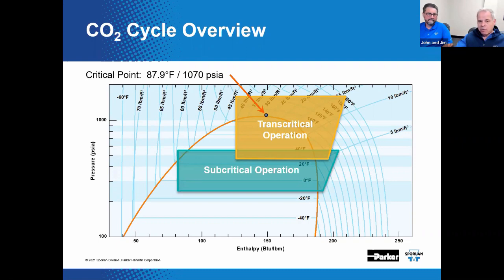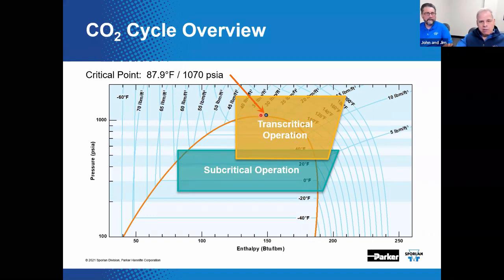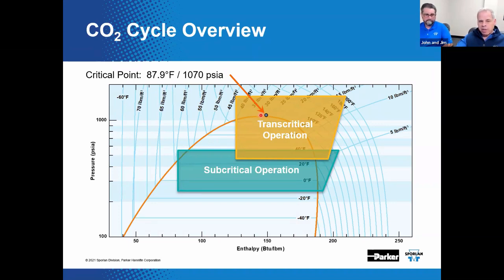Designs typically have two modes of operation. Could have transcritical and or subcritical. Now, what is the critical point? What does that mean? The critical point is up at the very top of the dome. Is that it right there? Yep. And basically above that point, you cannot achieve a state of saturation. And for CO2, that critical point is 87.9 degrees F. That's kind of low, isn't it? It's kind of low. By comparison, R404A has a critical point of over 160 degrees Fahrenheit. Wouldn't having a high critical point be a good thing on the selection for a refrigerant? It actually is a very good thing, yes.